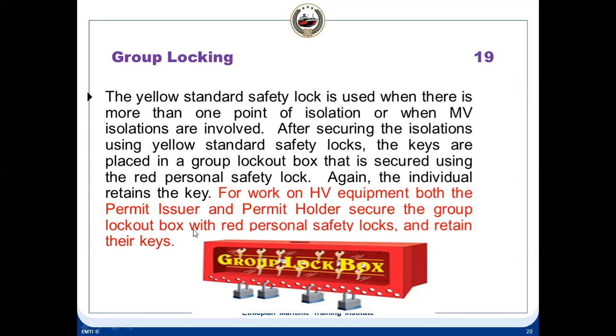It's also used in cases like when you're working with multiple locks on a single system. So this yellow standard safety lock is used when there is more than one point of isolation. After securing the isolation using yellow standard safety locks, the keys are placed in a group lock box that is secured using a red personal safety lock. You see, after you put all these keys inside, these all belong to the yellow locks, and it is finally locked by the red locks. Again, the individual retains the key. Now, for work on HV equipment, both the permit issuer and permit holder secure the group lockout box with red personal safety locks and retain their keys.